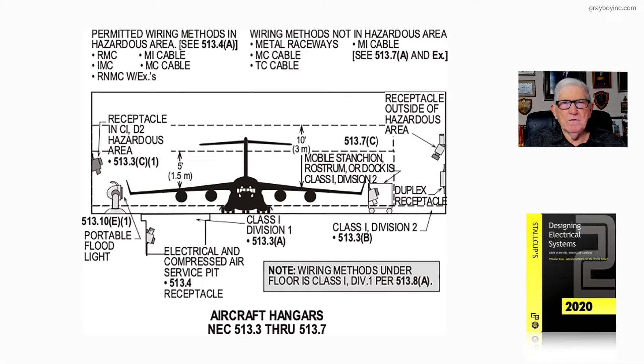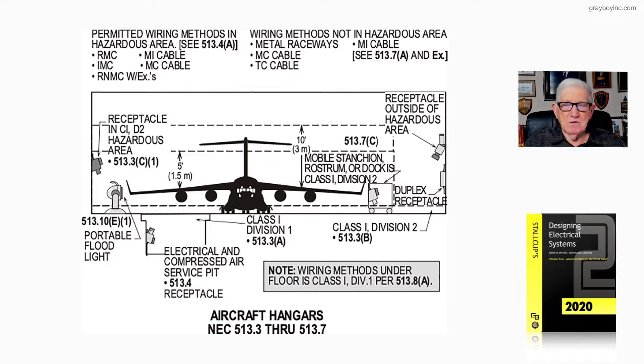Let's review figure 21-47, which deals with aircraft hangars in accordance with NEC 513.3 through 513.7. You're looking at a number of sections to get the overall picture. Starting at the top of the illustration, permitted wiring methods in hazardous areas are in accordance with 513.4a.